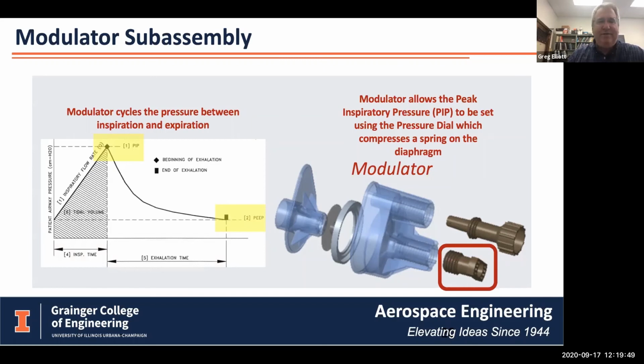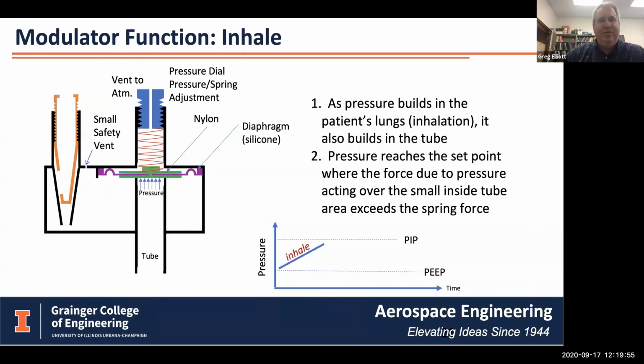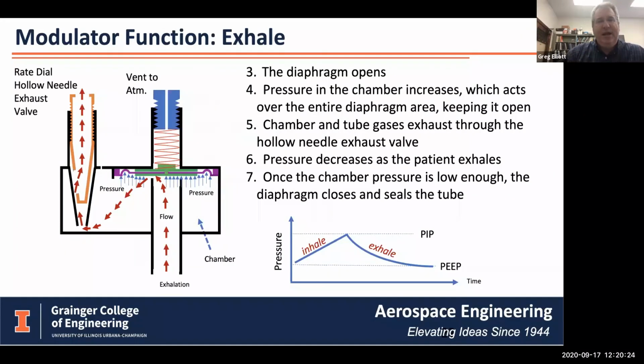Now, the logic of how this device works is pretty clever. Basically, you're pressurizing this tube and you're pressurizing the patient's lungs. As that pressure builds up, the diaphragm is closed, but you've set it with a spring tension. When the pressure gets high enough, acting over that area, it overcomes the spring tension and the diaphragm opens. The pressure flows out into a chamber that is pressurized, and so that pressure acts over a larger area, so the diaphragm stays open.